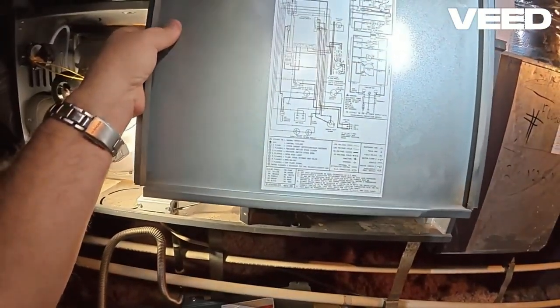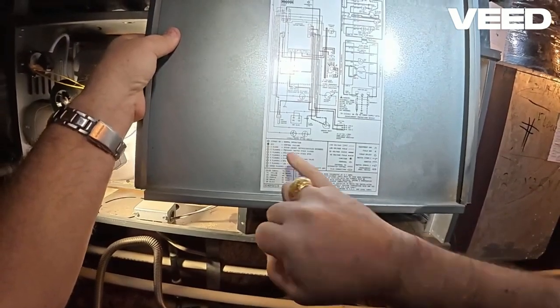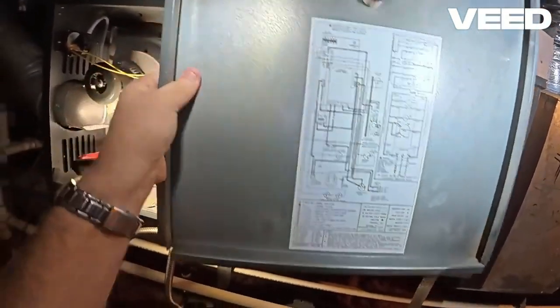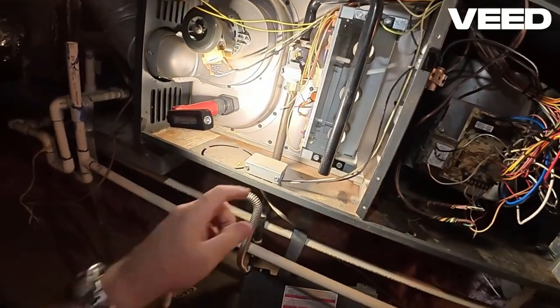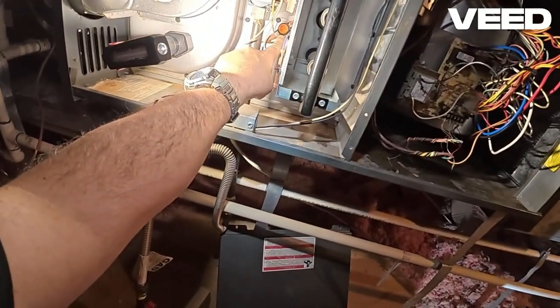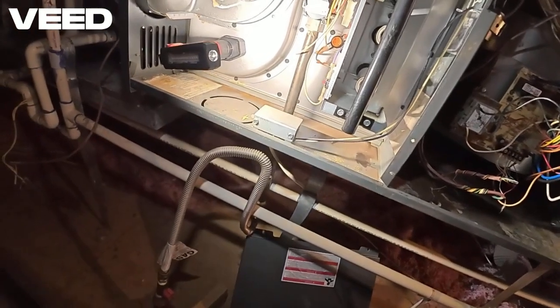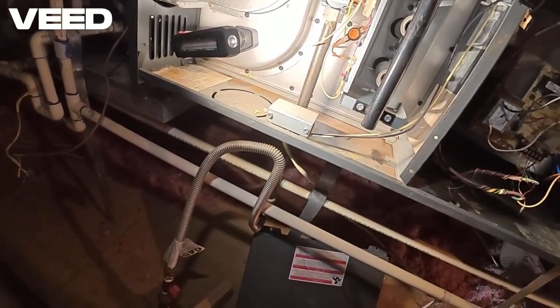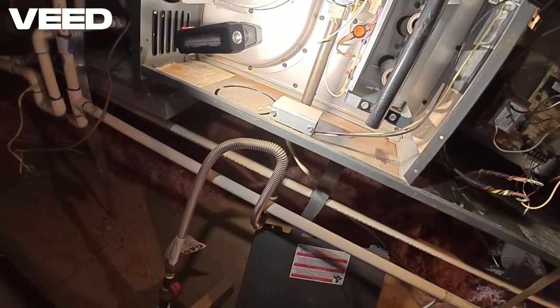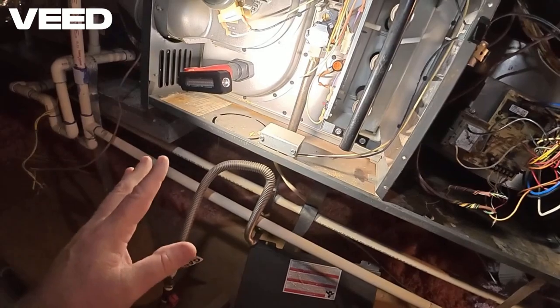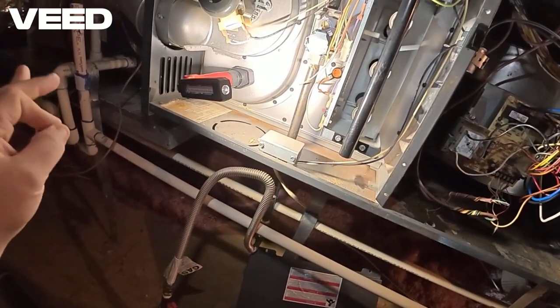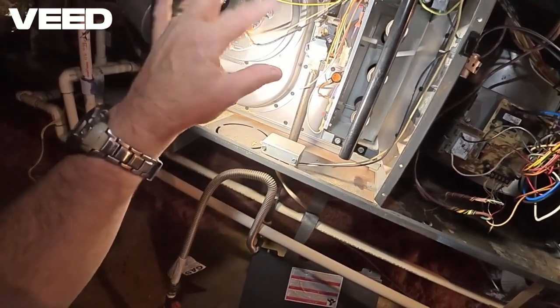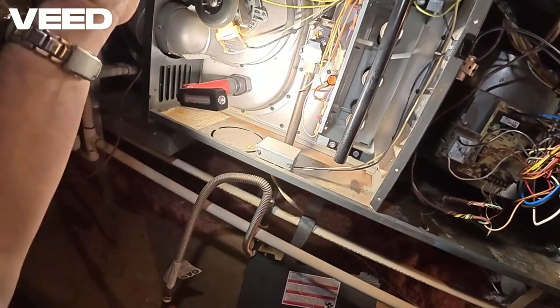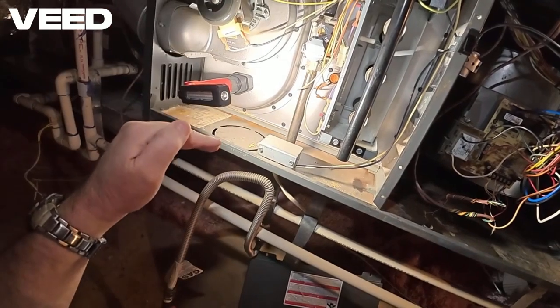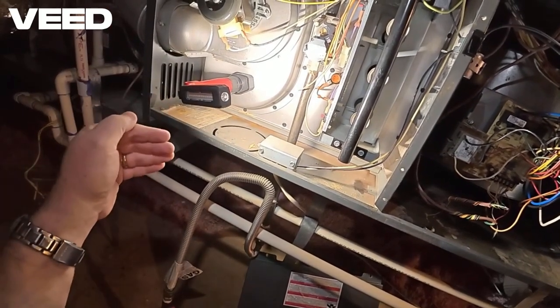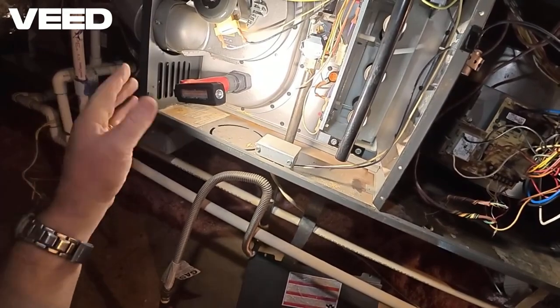If we look down here a bit more, we see also an open high limit. So the high limit is a switch. If you can see right back here in the back, there's an orange label on it, and it's labeled 170-30F. And what that means is at 170 degrees, that switch will open up, and not until it cools down 30 degrees or to 140 will it close again.